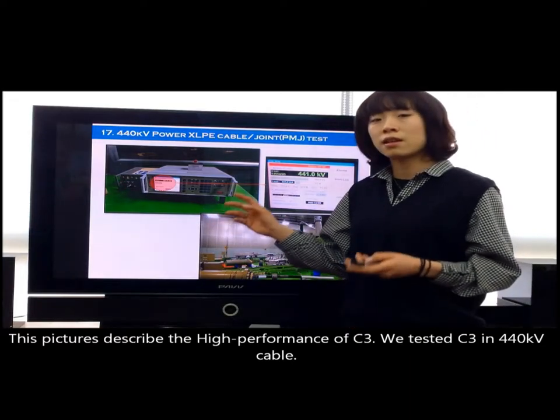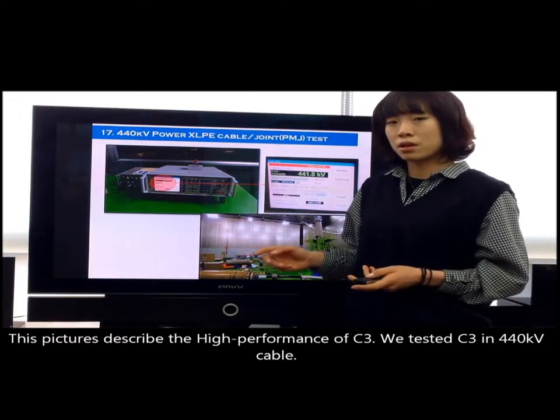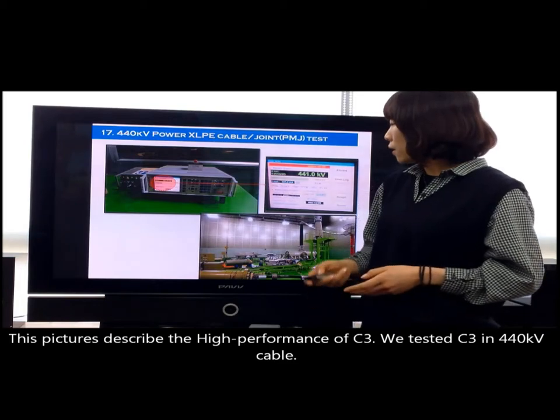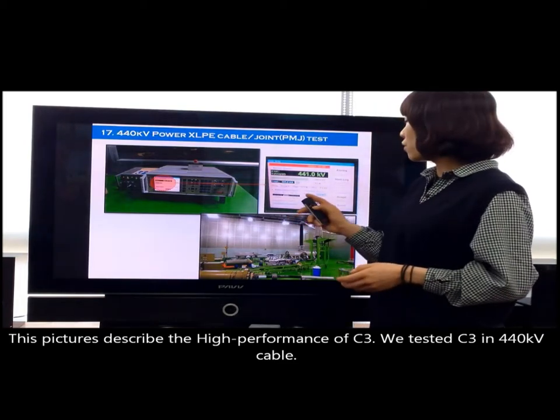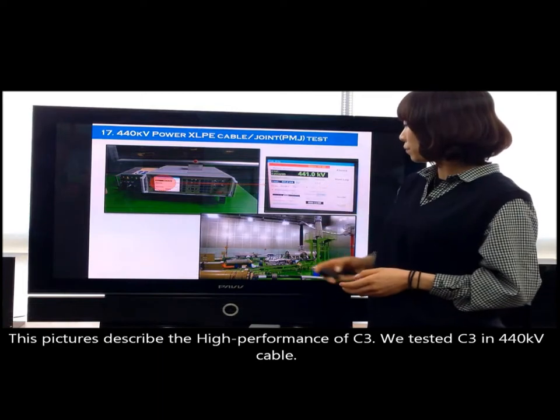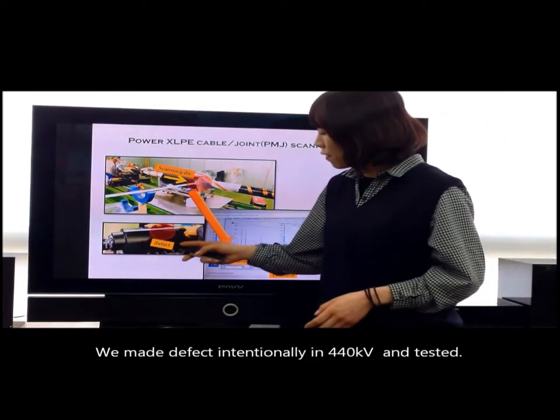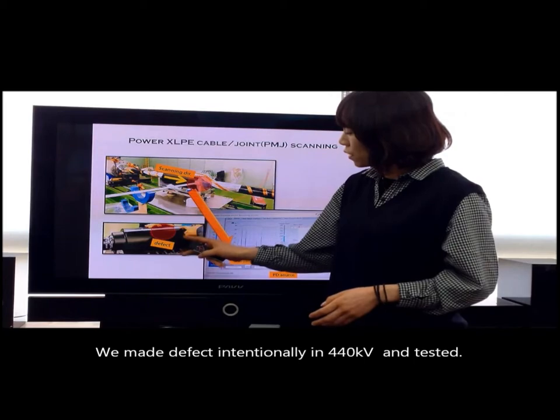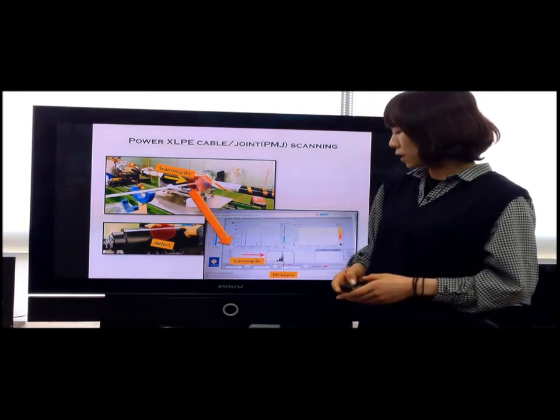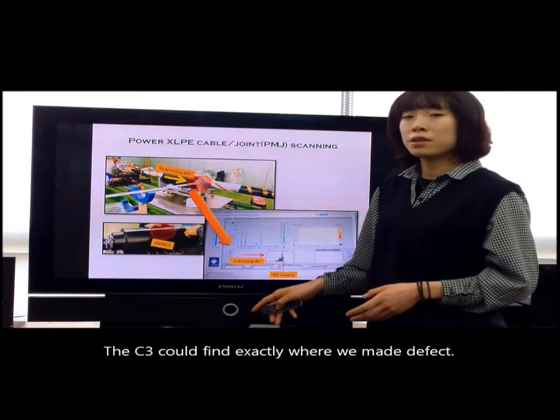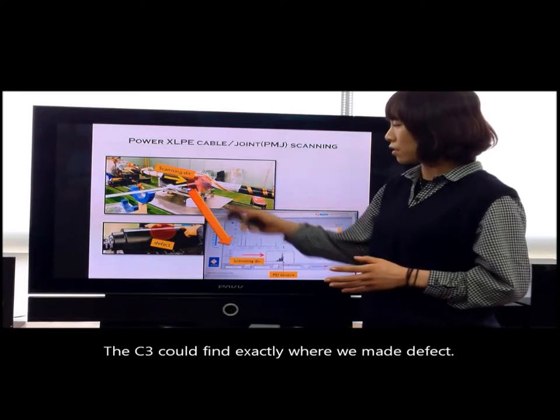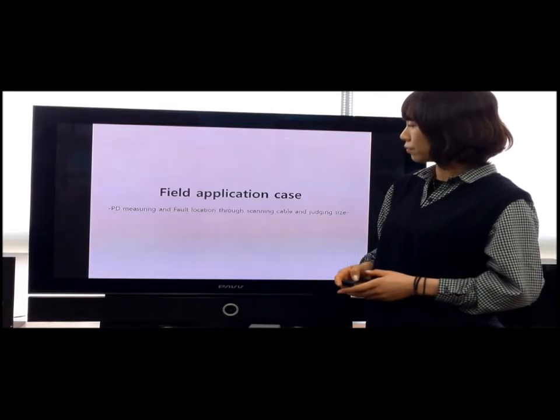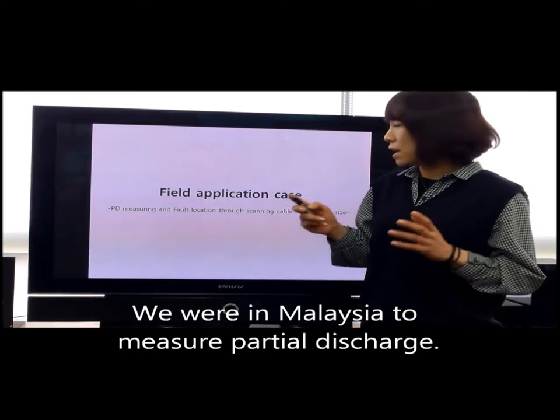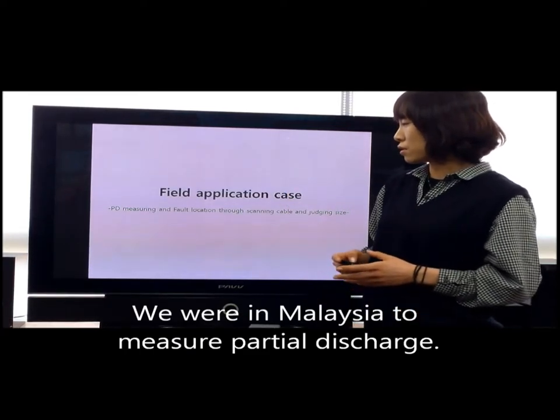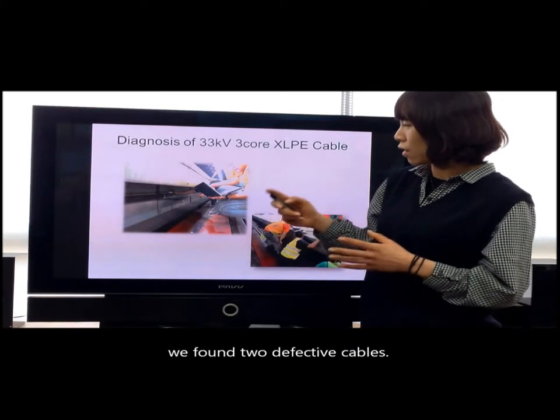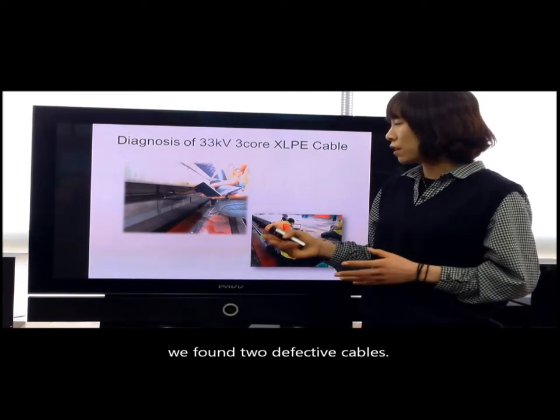And these pictures describe the high performance of C3. We tested C3 on a 440 kV cable. We made a defect intentionally in the 440 kV cable and tested. C3 could find exactly where we made the defect. We were in Malaysia to measure partial discharge, and we found 2 defective cables.